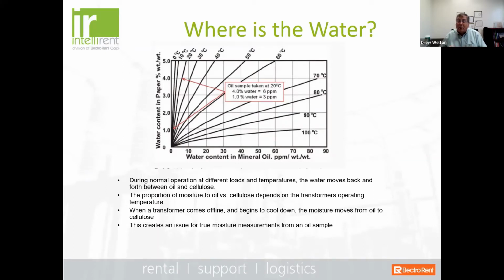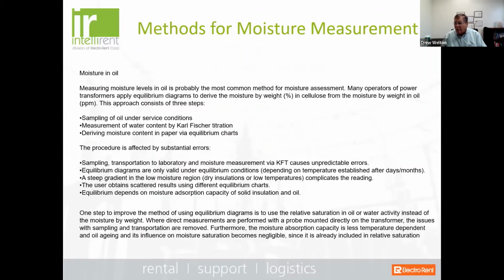So if you are going to do dielectric testing and diagnostic testing on your transformer, you take the transformer offline. The transformer starts to cool down naturally. But as the transformer cools down, the moisture goes from the oil back into the insulation. Now, this creates an issue for true moisture measurements from an oil sample, and there are a couple of issues surrounding what we call applying equilibrium curves. Unfortunately, this is the most common method of measuring moisture content in the oil.